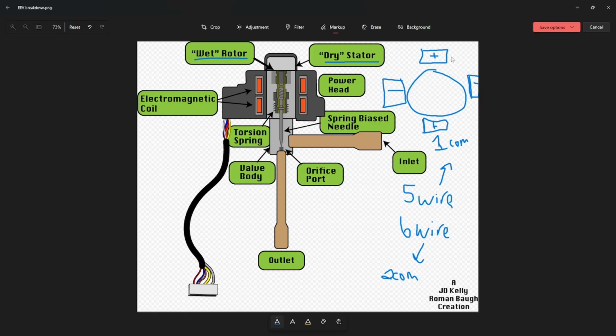And this creates a magnetic field which will drive that needle one direction or the other, depending on how it sends the voltage down our wire to power these magnetic coils. Now, you'll always have about 4 coils in the motor, which is why you'll always have 4 power wires to check to common.